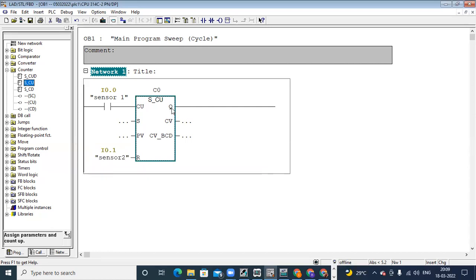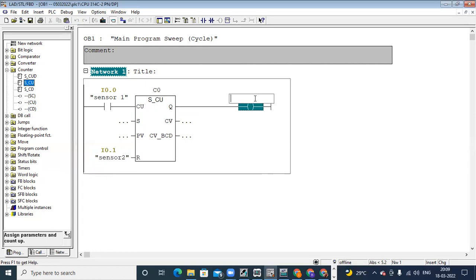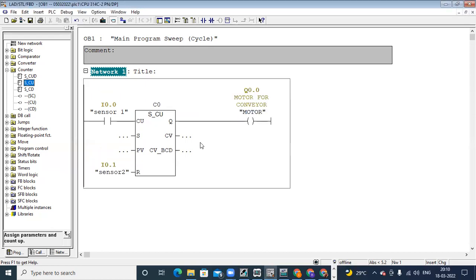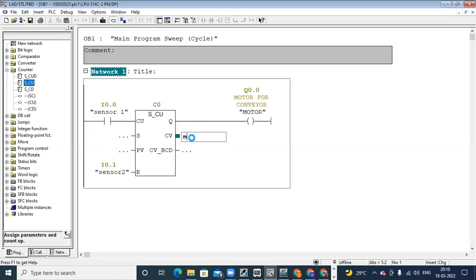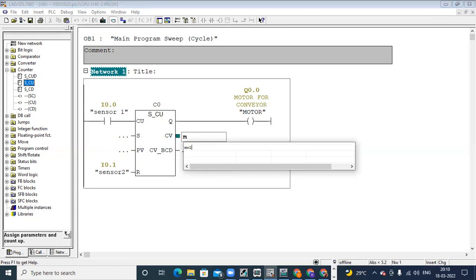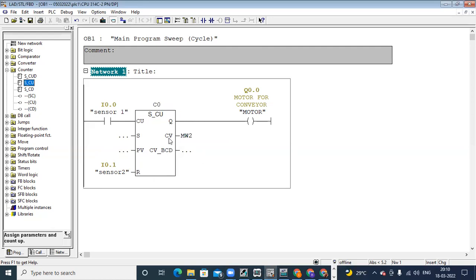Reset input is also boolean, like I0.1. On the output side, Q output is also optional — if you want to connect any output coil, use Q0.0. Then CV means count value — that is your counted value. The number of times the input is going on or off, your counter is incrementing by one, and that value is stored in CV. To read that value we need a memory address, so I am taking MW2 as a word memory to read the value from CV, because CV doesn't have a fixed address for calculations.